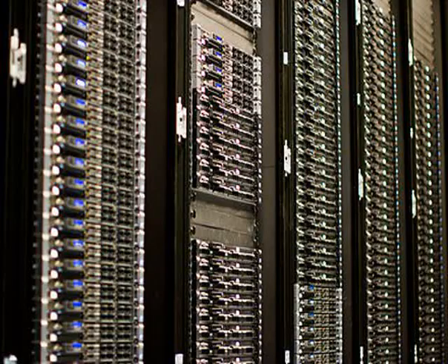The power used by the entire server farm may be reported in terms of power usage effectiveness or data center infrastructure efficiency. According to some estimates, for every 100 watts spent on running the servers, roughly another 50 watts is needed to cool them. For this reason, the siting of a server farm can be as important as processor selection in achieving power efficiency. Iceland, which has a cold climate all year as well as cheap and carbon-neutral geothermal electricity supply, is building its first major server farm hosting site.